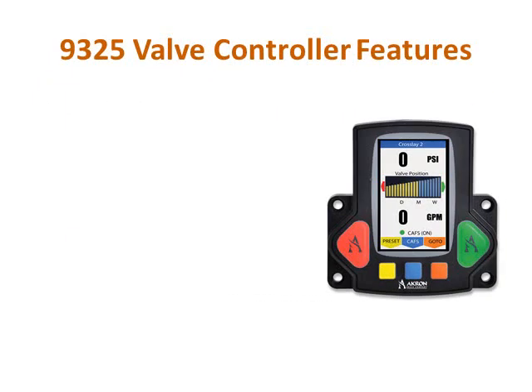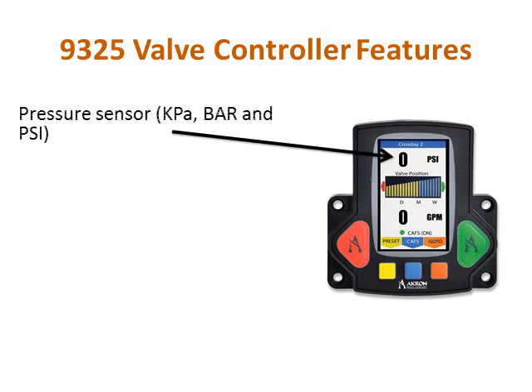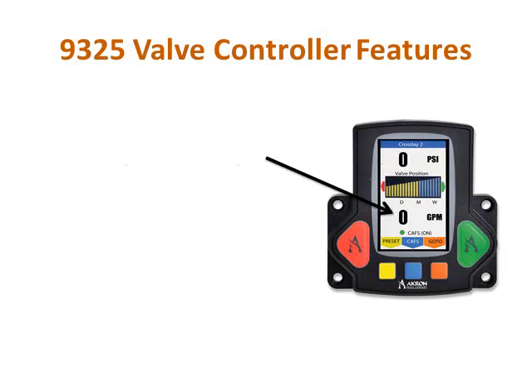The Style 9325 valve controller contains all of the basic features available on the 9323, plus many others. It has the ability to read and display the pressure in the line. The user can choose the desired display units, and these options are easily configured during the system setup. This controller can also read and display the flow. The user can choose from GPM or LPM for the on-screen flow display.